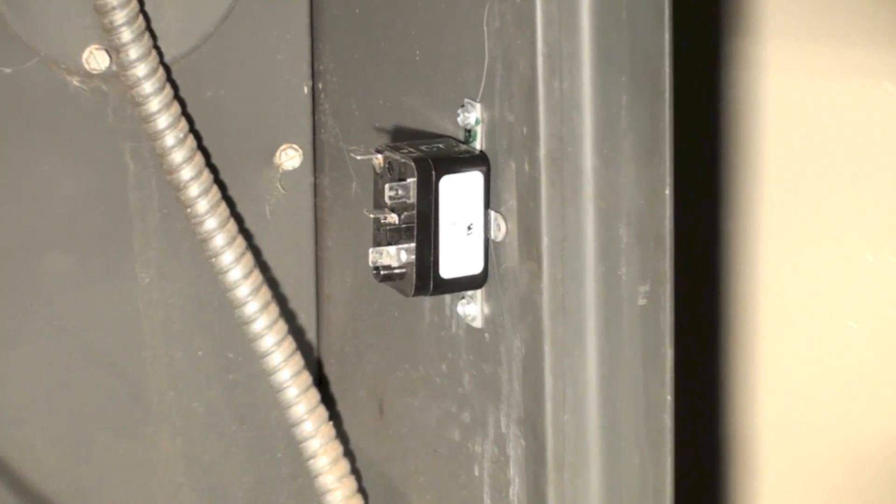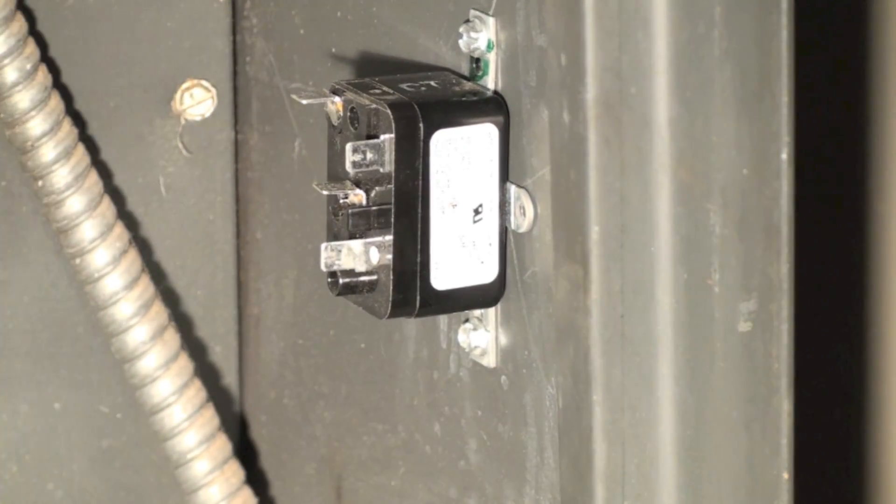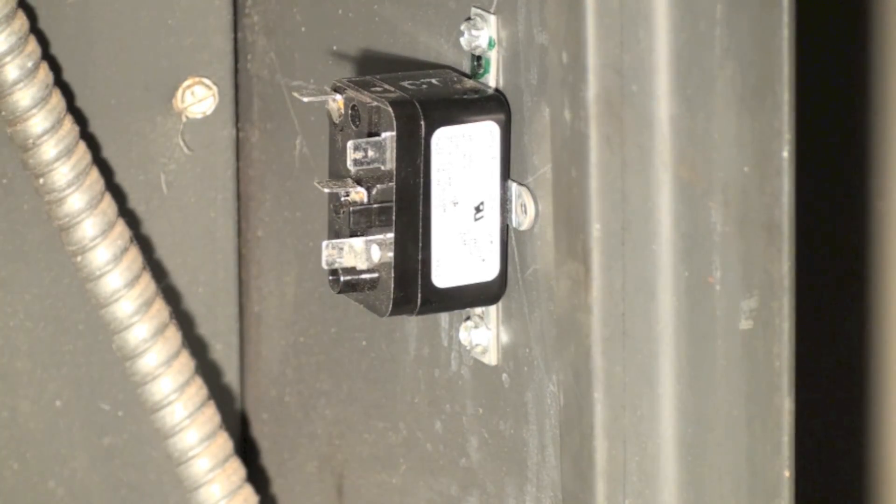You can see here the relay is mounted. This is using the relay I showed earlier. We usually call it a peanut relay because it's a low power relay. There's any number of relays you could use, but it has to have a 24 volt coil.